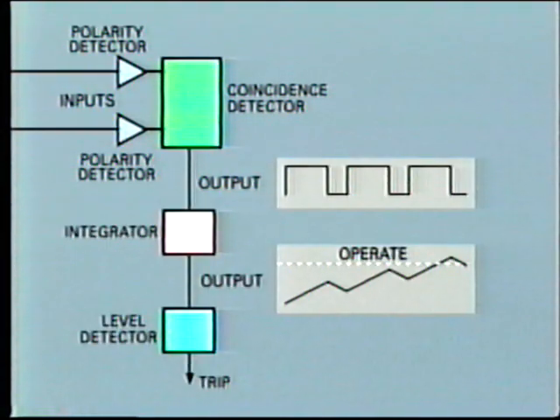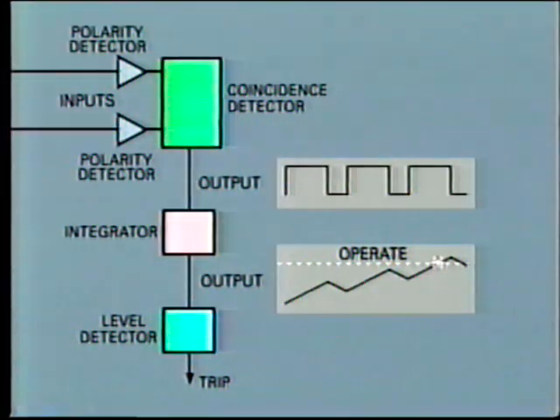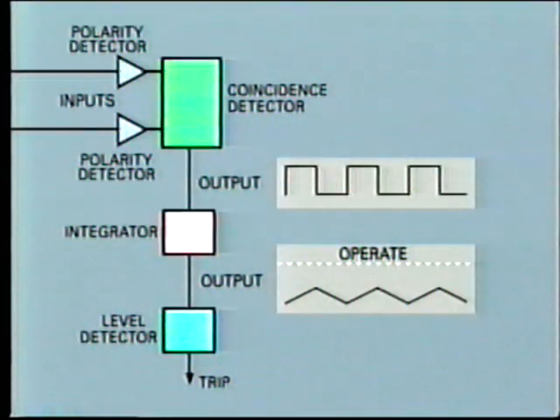The detector output is fed into an integrator where a capacitor is charged by the voltage pulses and discharged during the intervals. At low phase angle differences, the capacitor charge accumulates and rises to a preset tripping level. At higher phase angle differences, the capacitor voltage is repeatedly discharged and will not rise to the trip level. The specific phase angle for tripping is adjustable.